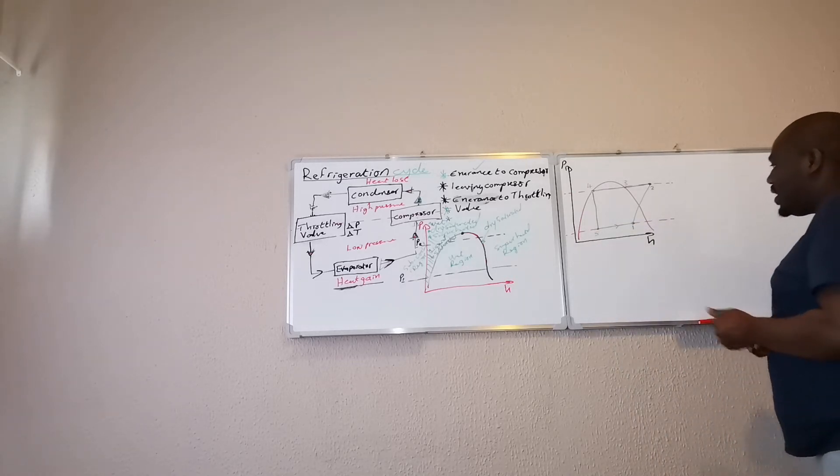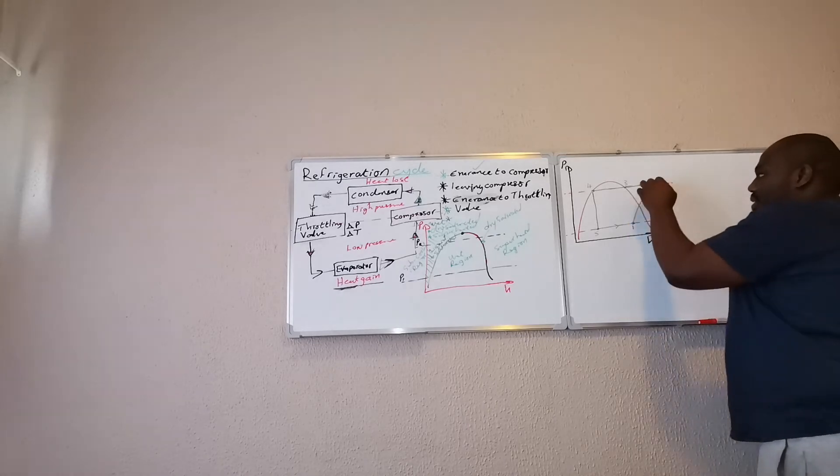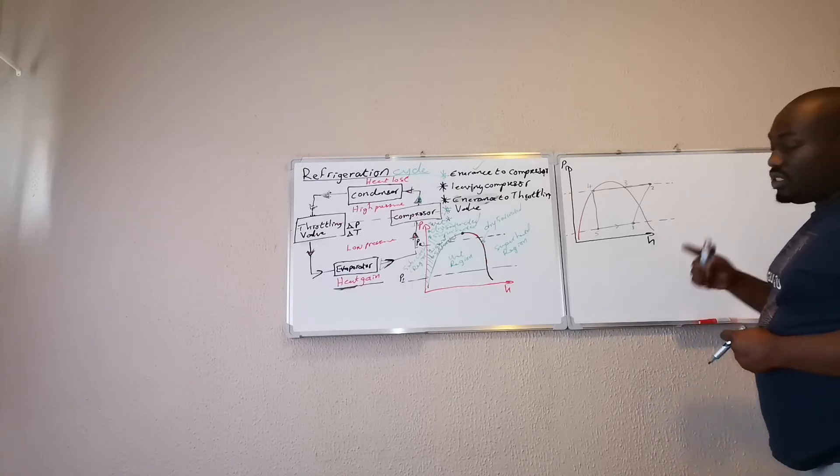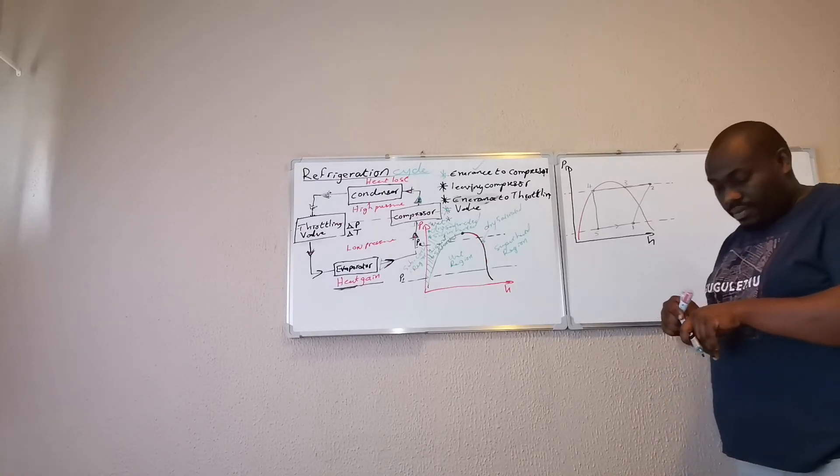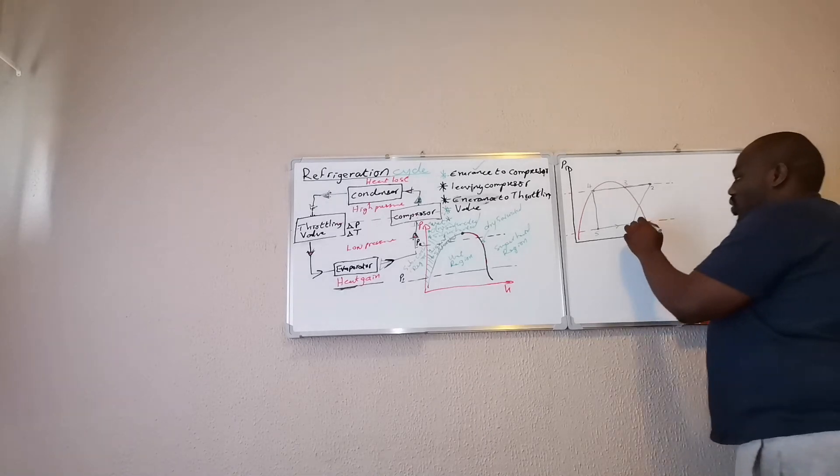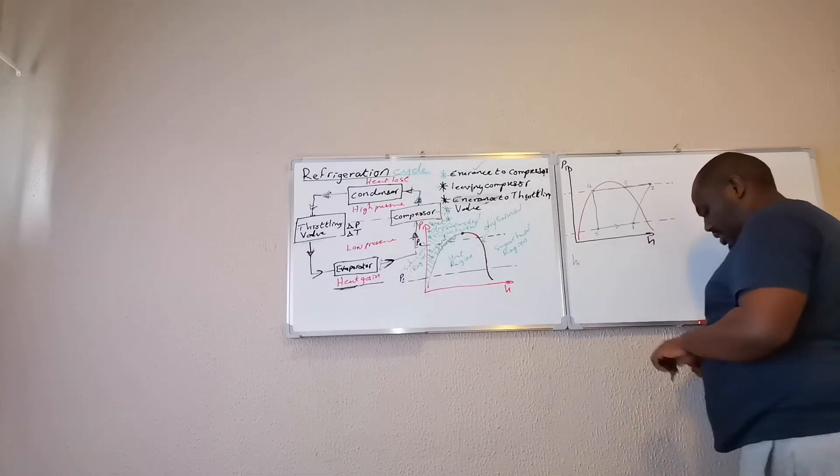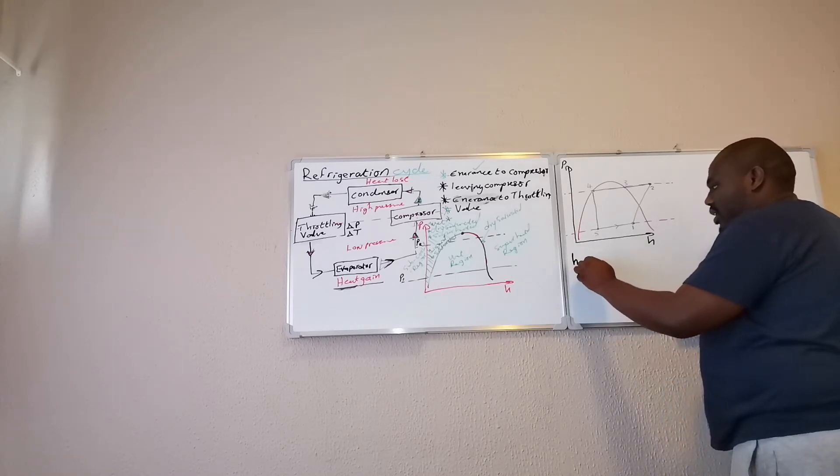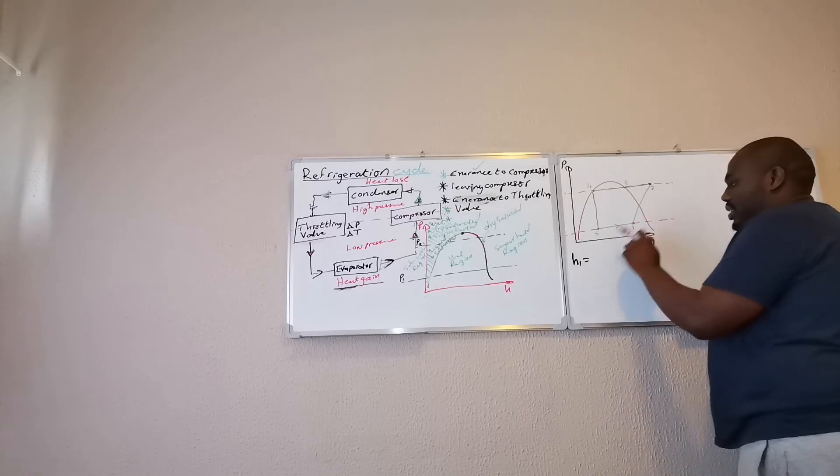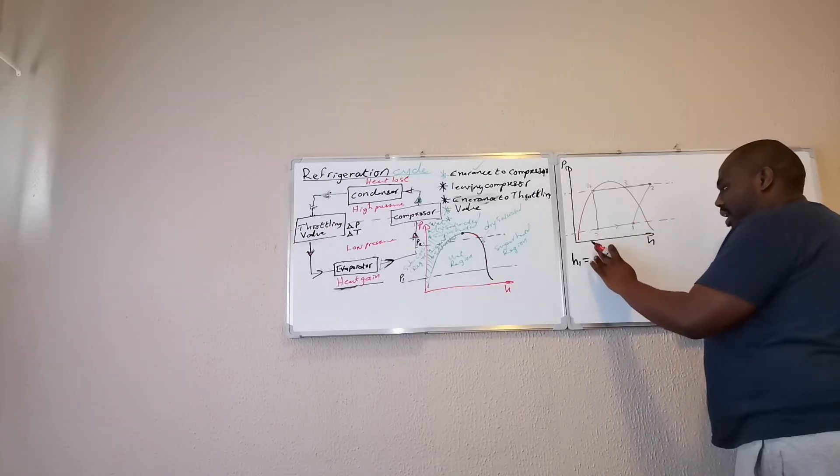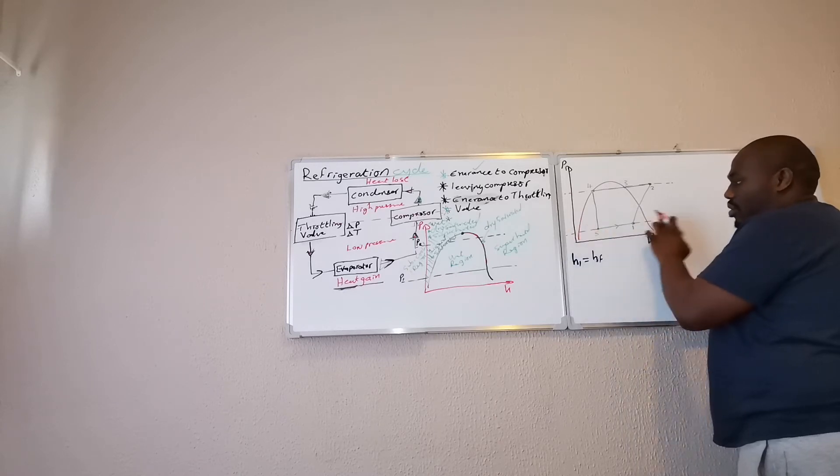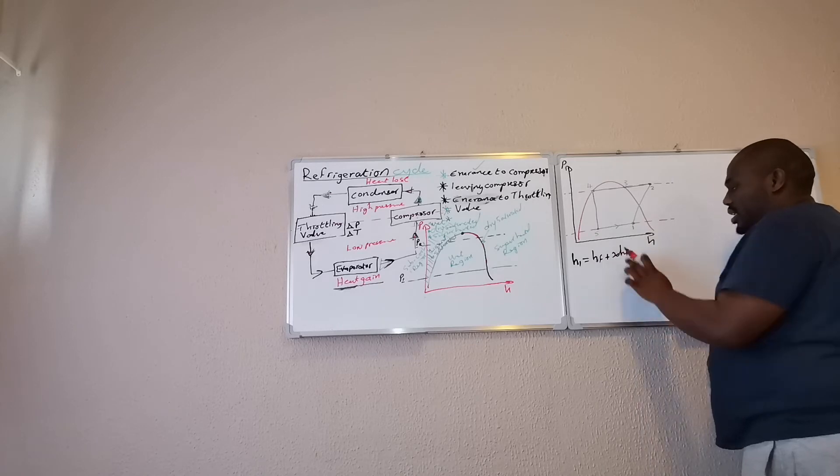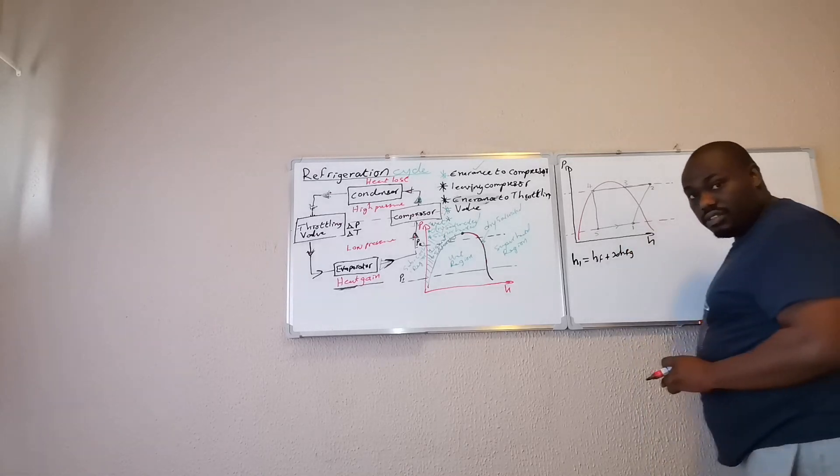So, how do I calculate the enthalpies at each of these points? Because I need the enthalpies to find out how this compressor is going to perform and so forth. So, to find H1, H1 is in the wet region. So, it would be HF at the lower pressure line plus X HfG at the lower pressure line. X would be your dryness fraction.